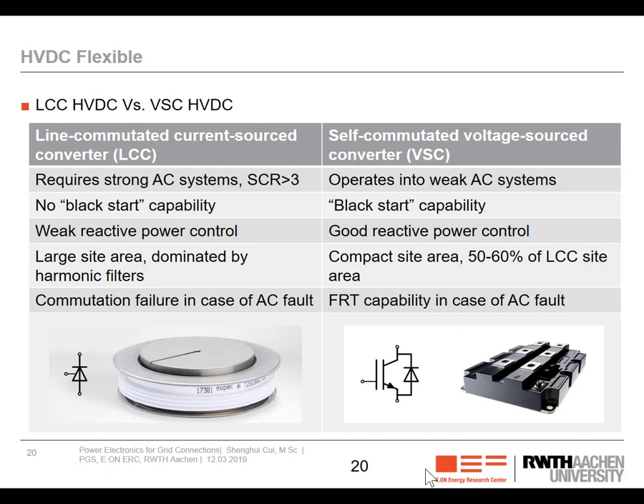At first, we can start with high voltage transmission. For high voltage DC transmission, there are two different types. One is the so-called line commutated current source converter, which is mainly based on thyristor technology, and the other one is called self-commutated voltage source converter technology. Of course, this is a very old and mature technology. The benefit is that it is extremely efficient and extremely robust, but the problem is that it always requires strong AC systems to interconnect. Here, a strong AC system means a short circuit ratio of at least over 3.